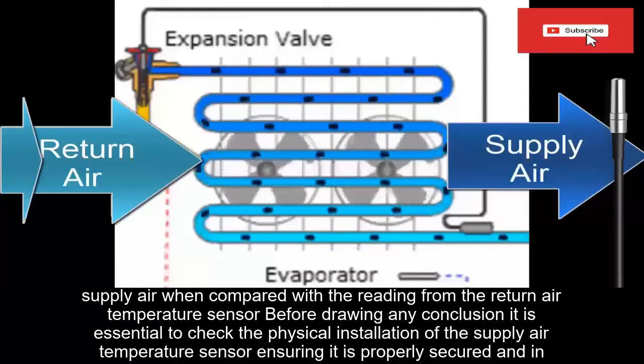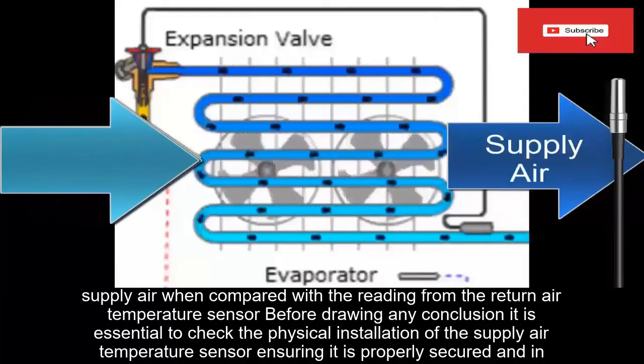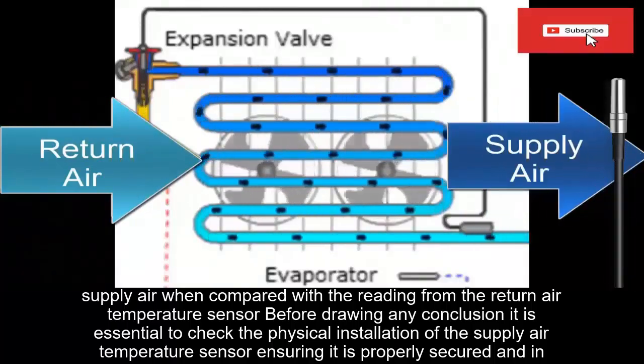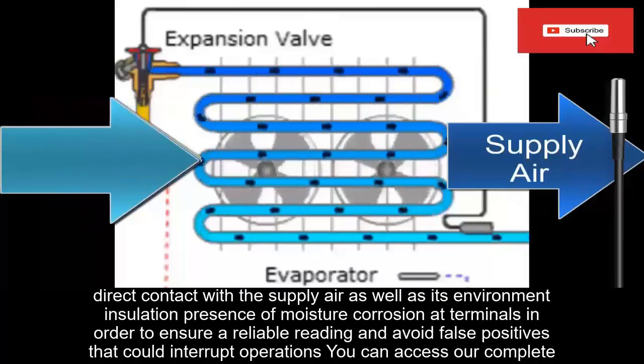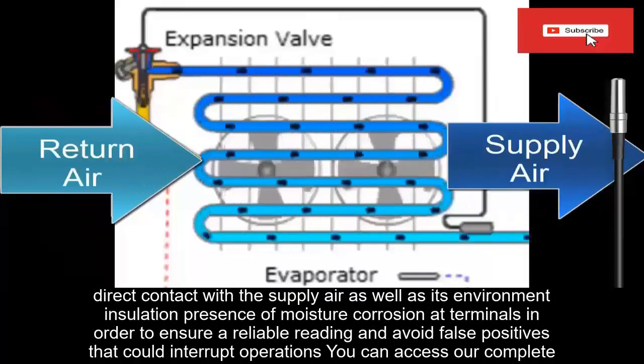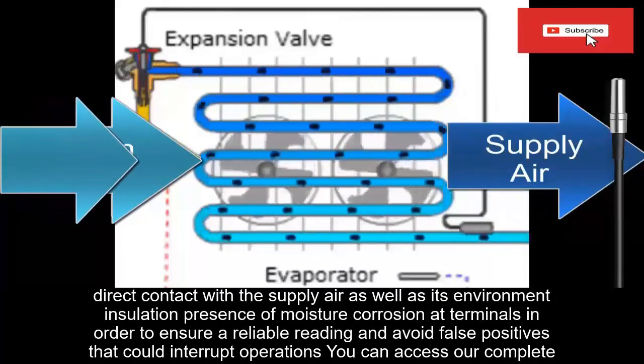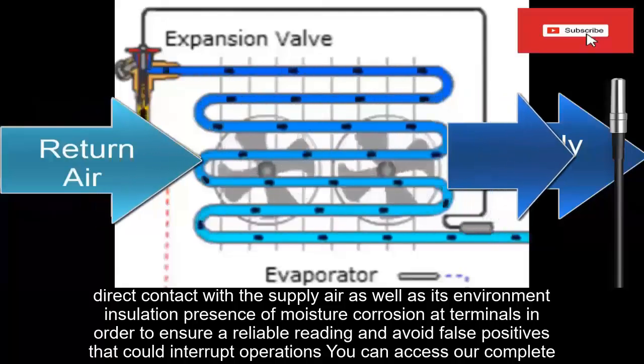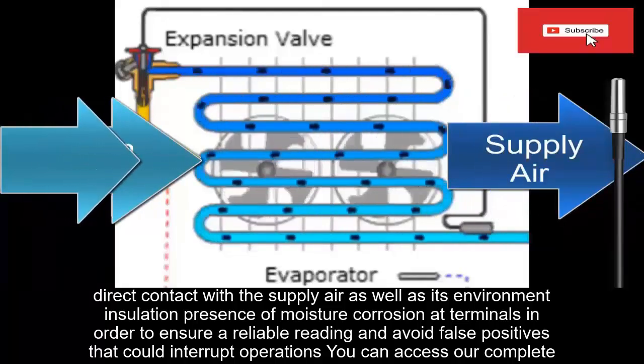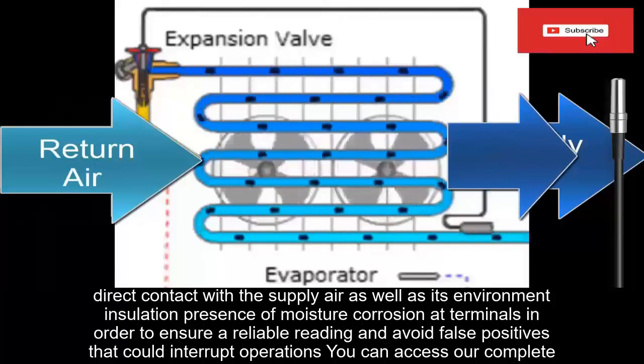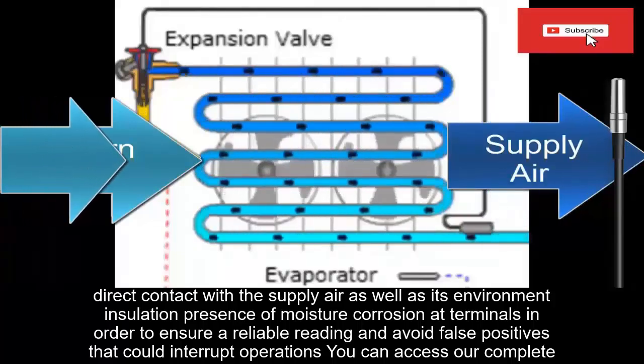Before drawing any conclusion, it is essential to check the physical installation of the supply air temperature sensor, ensuring it is properly secured and in direct contact with the supply air, as well as its environment, insulation, presence of moisture, and corrosion at terminals, in order to ensure a reliable reading and avoid false positives that could interrupt operations.